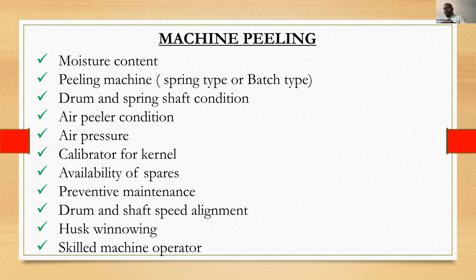What will happen - the air peeler will make you cry sometimes if you don't have proper pressure or don't know the exact analysis of air consumption: how many CFM required, how much CFM we have, what is the consumption of air. If we don't have that, it will make us cry. We have to do more paperwork on that. Let me share my point of view - we have around 5 peeling machines.